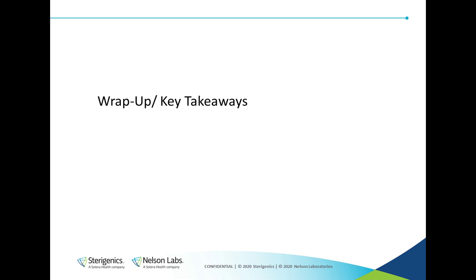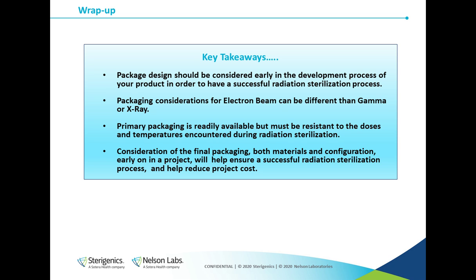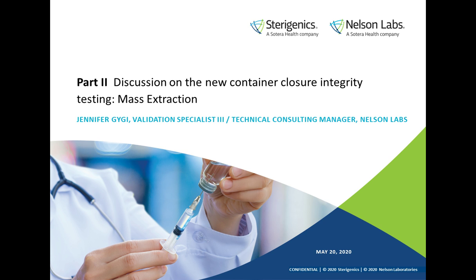And lastly, just a quick wrap-up and some key takeaways from my part of the presentation. I hope the key takeaways for today are that package design should be considered early in the development process of your product in order to have a successful radiation sterilization process. Packaging considerations for electron beam can be different than gamma or X-ray. Primary packaging is readily available, but must be resistant to the doses and temperatures encountered during radiation sterilization. And finally, consideration of the final packaging, both materials and configuration, early on in a project will help ensure a successful radiation sterilization process and will help you reduce project cost.